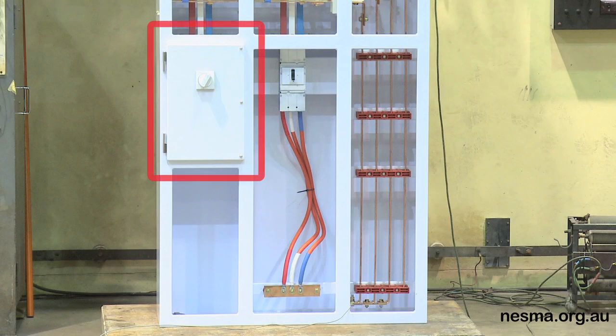Test 3, which is a standard arcing test started on the load side of a circuit breaker. It will be performed with just a piece of 20 amp fuse wire on the load side of the breaker. Thanks, Max. Our objective is to show pressurisation of a functional unit and the output of a circuit breaker in conjunction with arcing from a load side fault when performing a fault clearance within its capabilities. It's similar to test 2, except we've got a door on it this time, so let's see what happens.